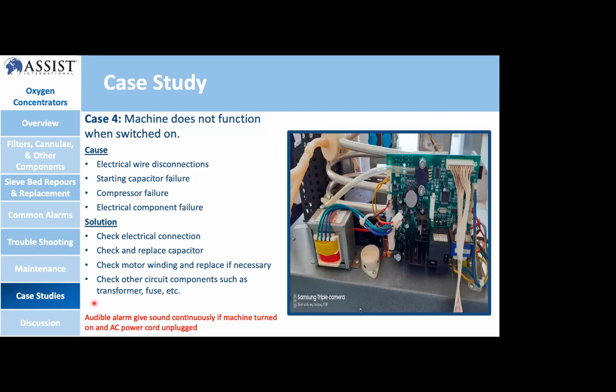So as a solution, we normally check electrical connections, and we tighten connections if there is a loose connection, and we replace the capacitor in some cases, and we check the motor winding and replace it. So these are the activities we did in these last weeks. That means we normally replace motors, compressors in some machines. And we check other circuit components such as transformer, fuse, relay, which are found on circuit boards. And if the power does not reach the PCB and we switch the machine on, we get continuous alarm sounding. And that means even though power is delivered to the machine, it is not working.